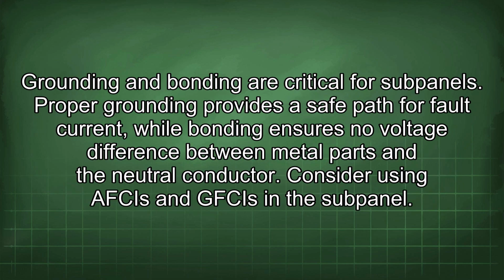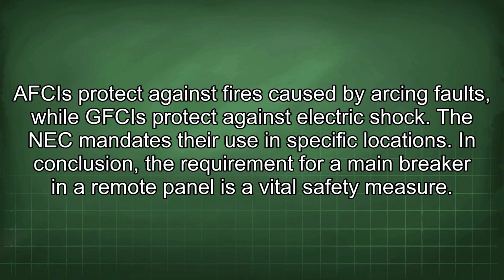Grounding and bonding are critical for subpanels. Proper grounding provides a safe path for fault current, while bonding ensures no voltage difference between metal parts and the neutral conductor. Consider using AFCIs and GFCIs in the subpanel. AFCIs protect against fires caused by arcing faults, while GFCIs protect against electric shock. The NEC mandates their use in specific locations.